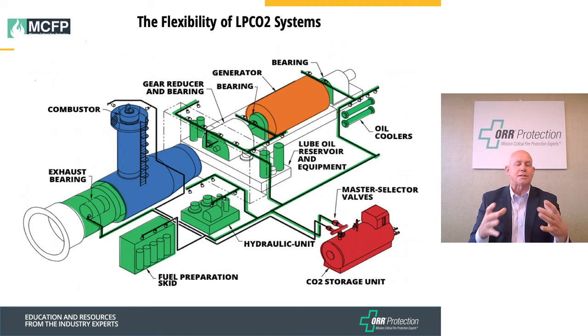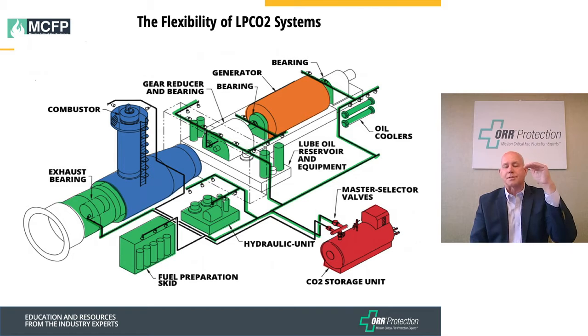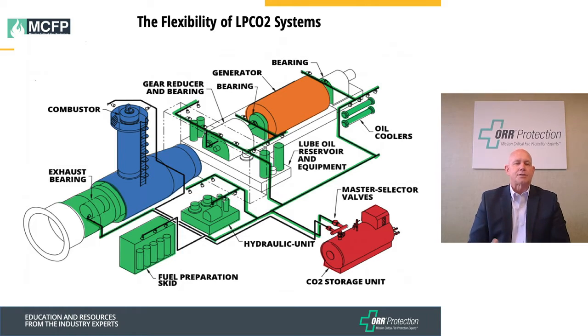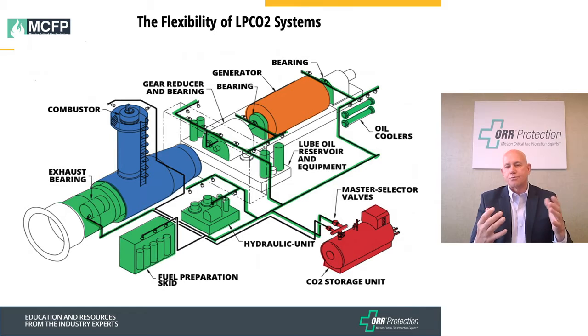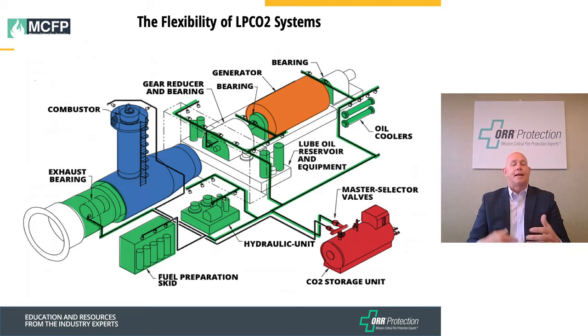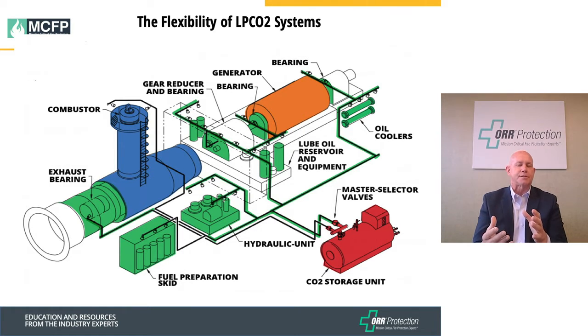The benefit of a bulk CO2 system is that a truck comes in, backs up to the bulk storage, fills it up, and you're done — instead of pulling out all individual bottles. A system this size can be a 12-ton, 8-ton, or 4-ton unit. The largest high pressure CO2 cylinder is about 100 pounds, so imagine how many bottles a 12-ton system would require. That's why low pressure is so widely used in power generation and roll mill industrial applications.